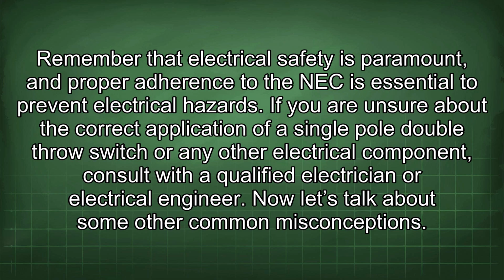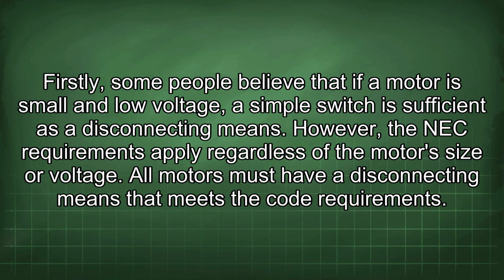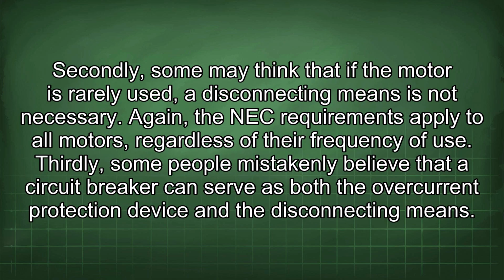Now let's talk about some other common misconceptions. Firstly, some people believe that if a motor is small and low voltage, a simple switch is sufficient as a disconnecting means. However, the NEC requirements apply regardless of the motor size or voltage. All motors must have a disconnecting means that meets the code requirement. Secondly, some may think that if the motor is rarely used, a disconnecting means is not necessary. Again, the NEC requirements apply to all motors, regardless of their frequency of use.